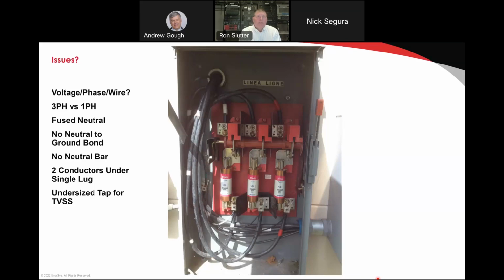So really what you have to do is configure the bar so you have inputs and outputs. If I walk into a facility and I see everything on one side, which I see most of the time, I can instantly tell you that it's not set up right. And unfortunately, if they're installed in the building, they're usually very hard to fix because they're either in the concrete, or they're routed all the way through the building together, right? So you really need to get that right at time of installation.